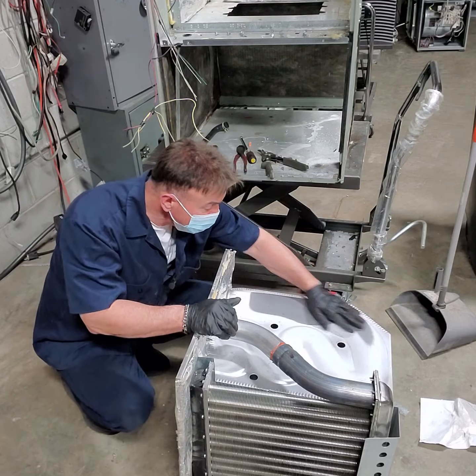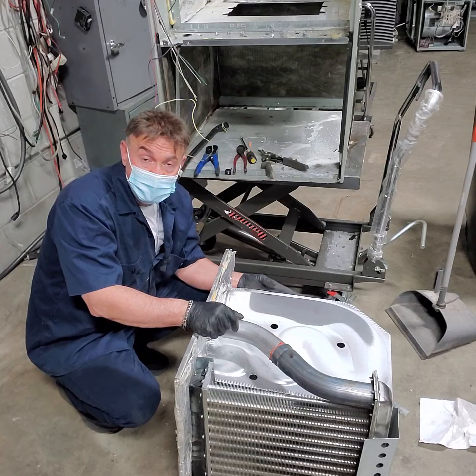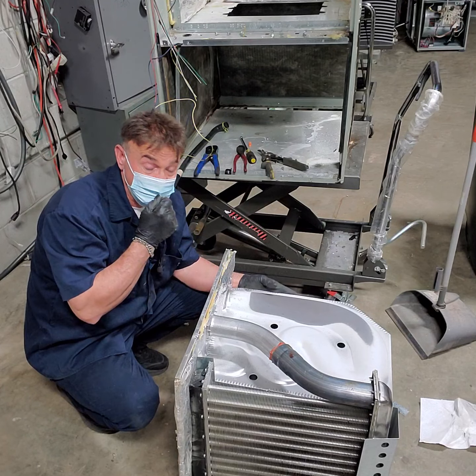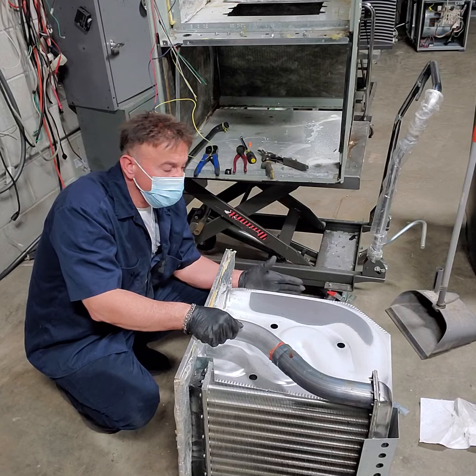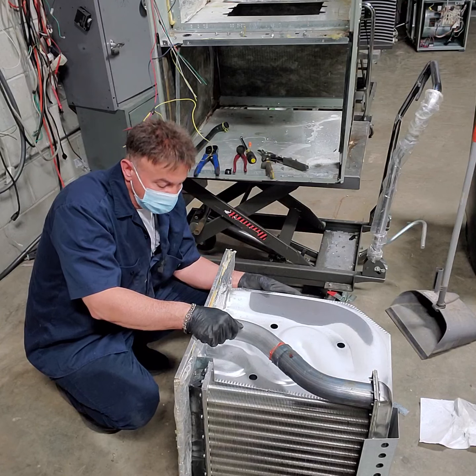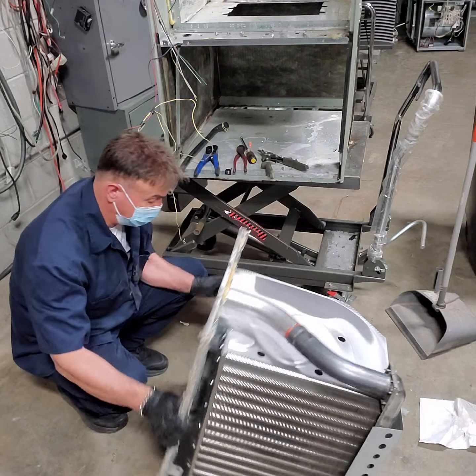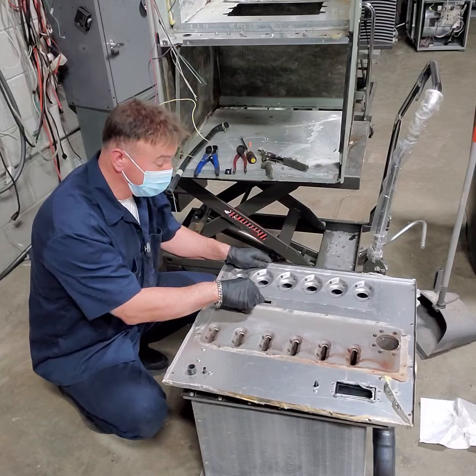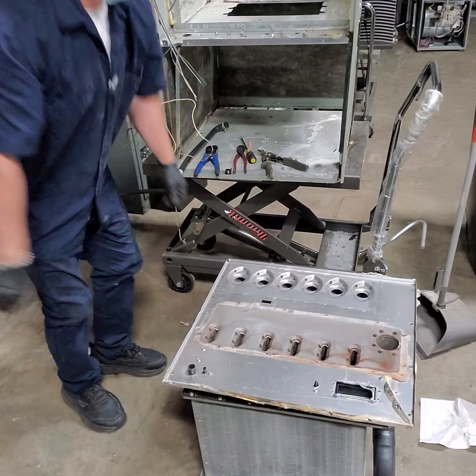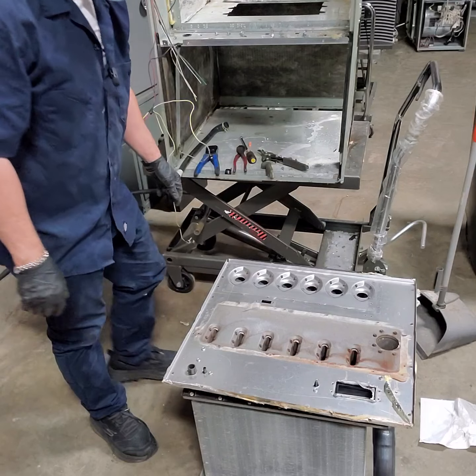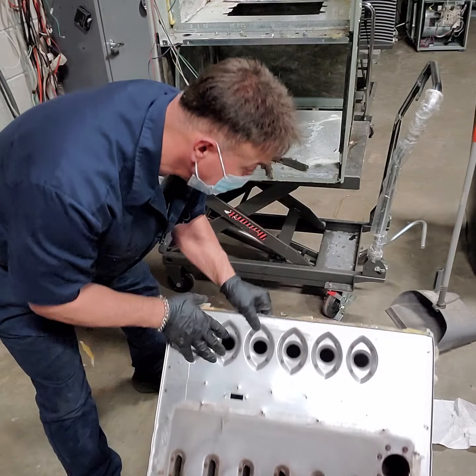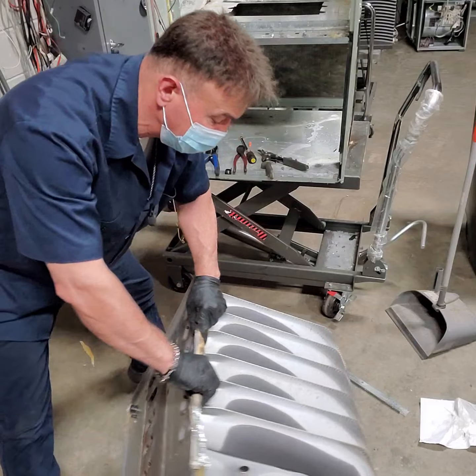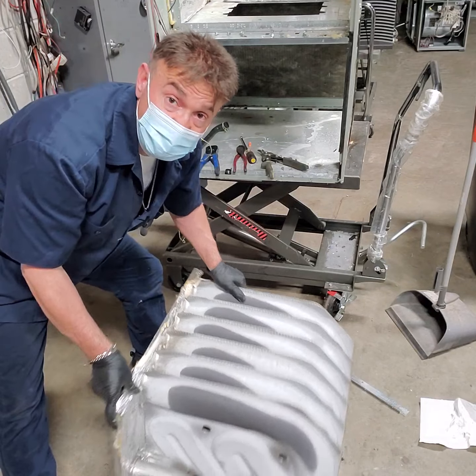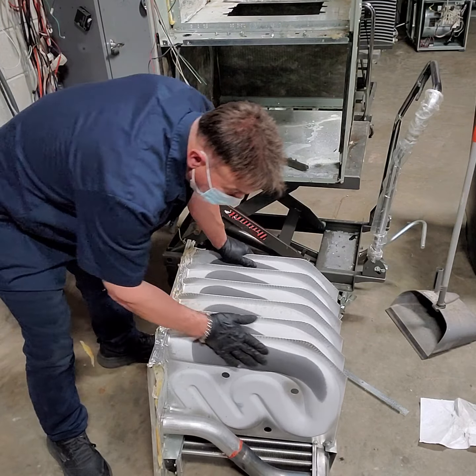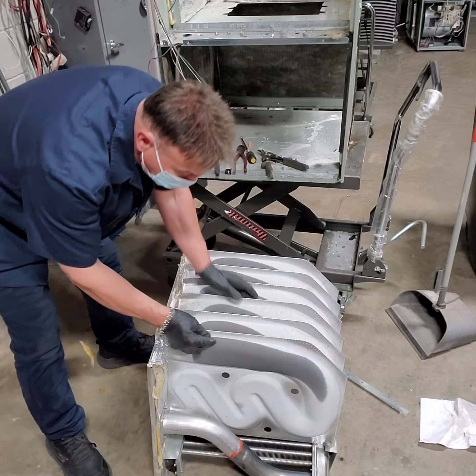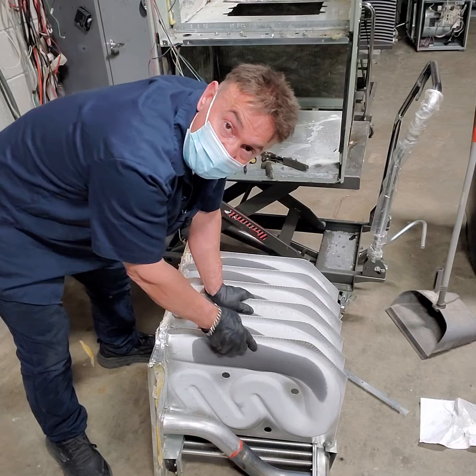Now if you see this here, that means the burners were not adjusted. So at some point, the limit switch, which sits here and monitors the temperature of the air, was not able to protect the heat exchanger from frying. You see these marks? Sometimes it can crack. You can see a crack in here.